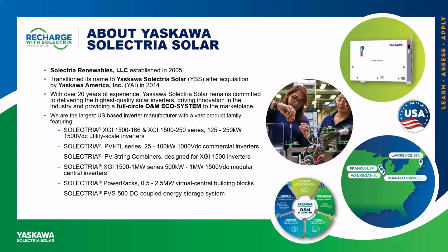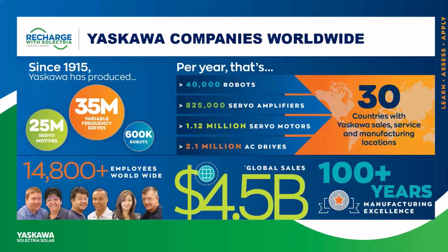We also have our power racks. These are powder-coated steel racks that can accommodate 2 to 8 inverters and are pre-wired with a project-specific AC combiner. Our power rack solution is 100% U.S. domestic content and fully BABA compliant if you do have federal or municipal jobs. We also offer our PVS 500 system, which is a 500 kilowatt DC coupled energy storage system, which we've offered for about 4 years. I'll turn to Yaskawa now, and you guys can advance that slide.